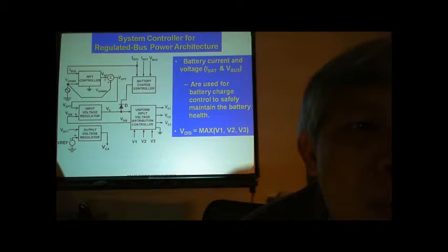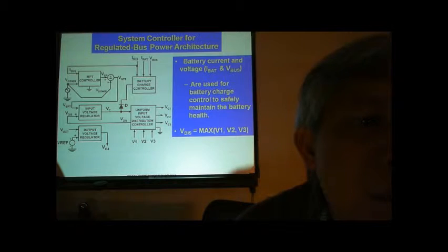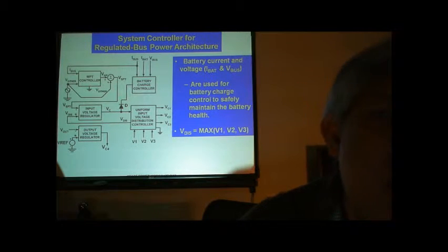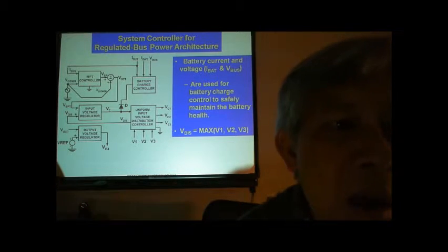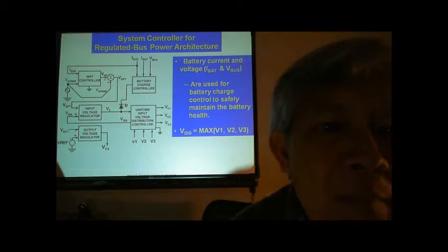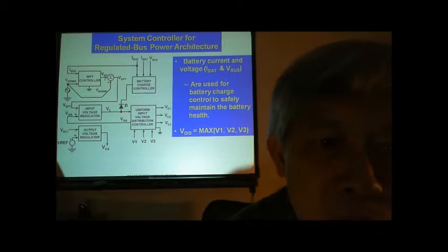VSP is the peak power point voltage candidate generated by the MPT controller using two signals. One signal is total sourcing current I bus and the other signal is the AC dither signal V dither. V dither is a sinusoidal signal of low frequency that is generated internally by the MPT controller. Usually, V dither has the same AC voltage ripple across sourcing voltage V1, V2 or V3.